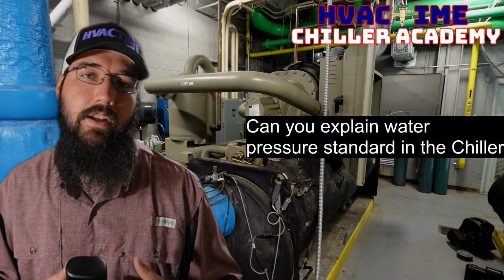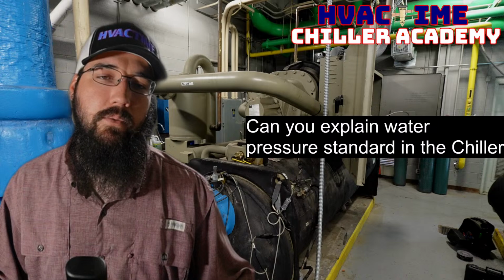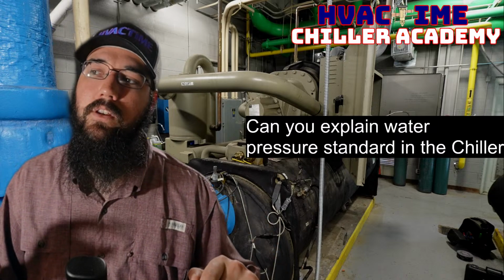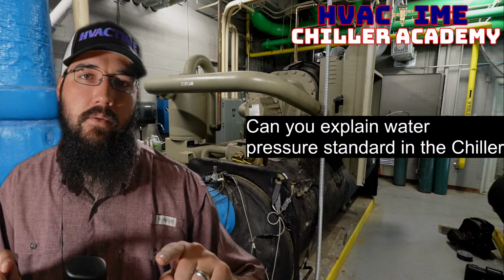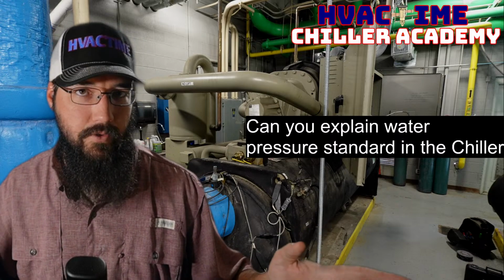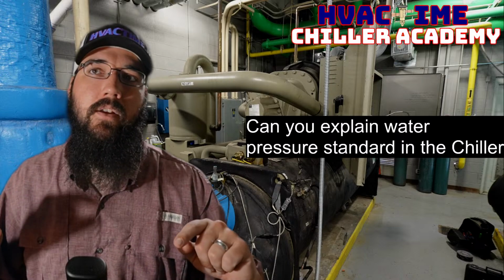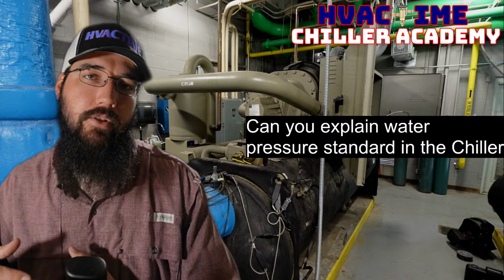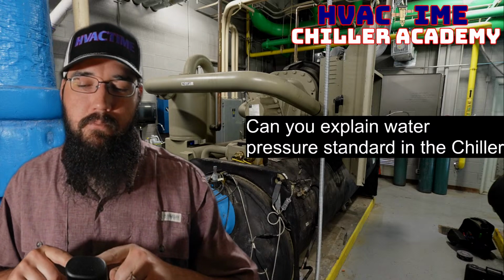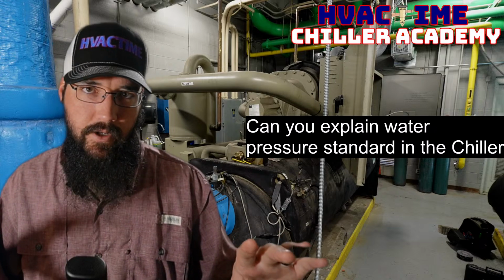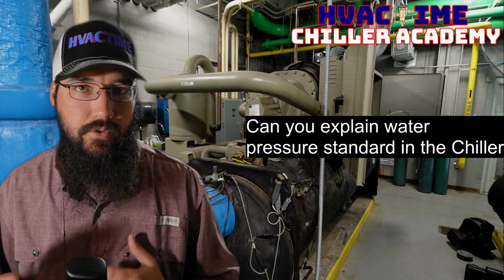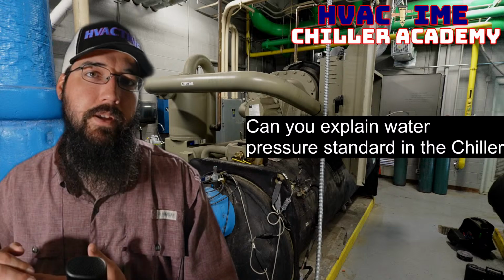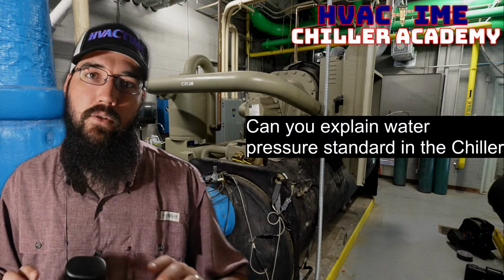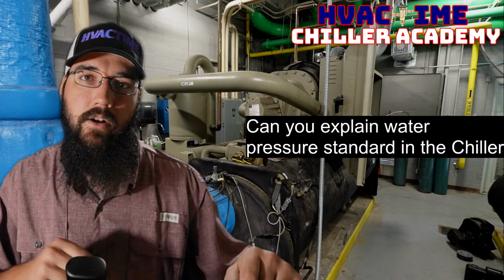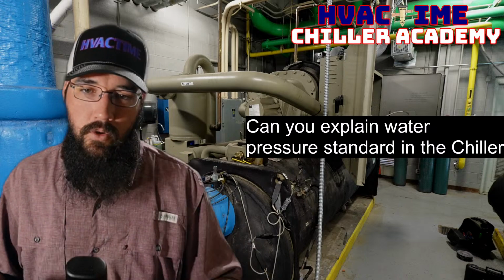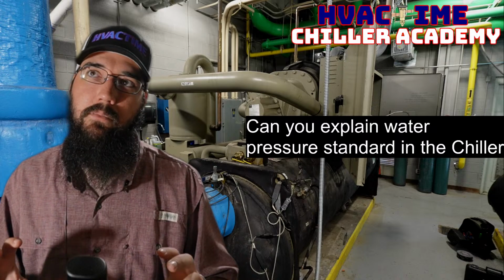So you'll take that DP, and that gives you a reference. Now, this is something we have to be careful with. With a valve or a strainer, the more pressure drop you have across a strainer, the less flow that strainer actually has. This is actually a reverse condition when it comes to a heat exchanger. The more differential pressure you have across the heat exchanger, the more GPM you will have. So that's an important distinction right up front. If we want more GPM, we need a higher DP. And this is a separate deal from a strainer or a valve, two different principles here.